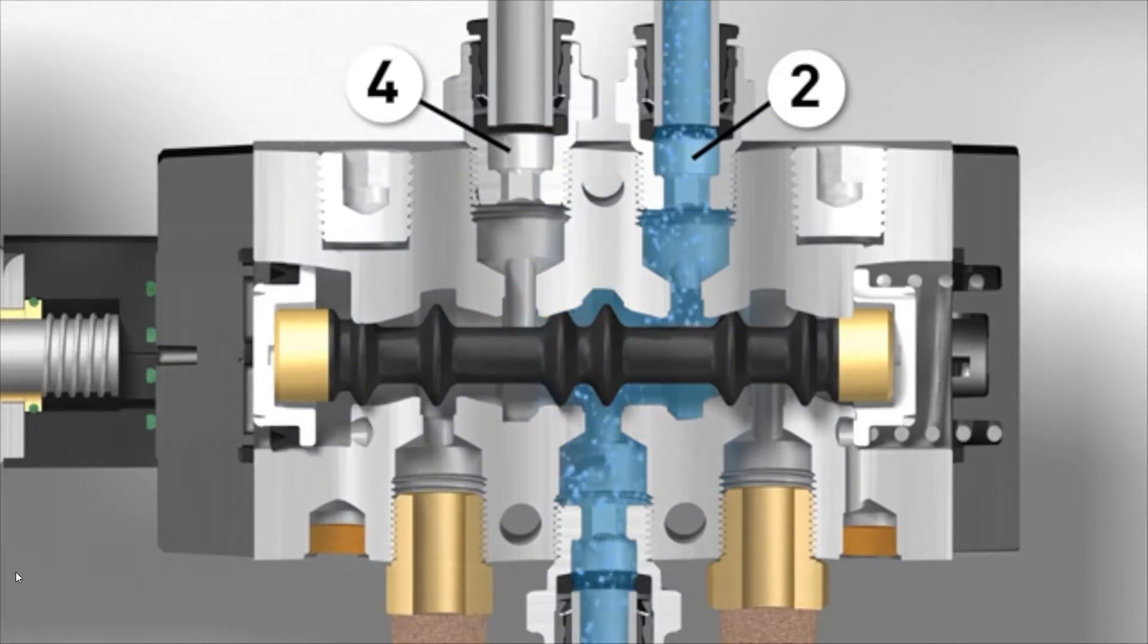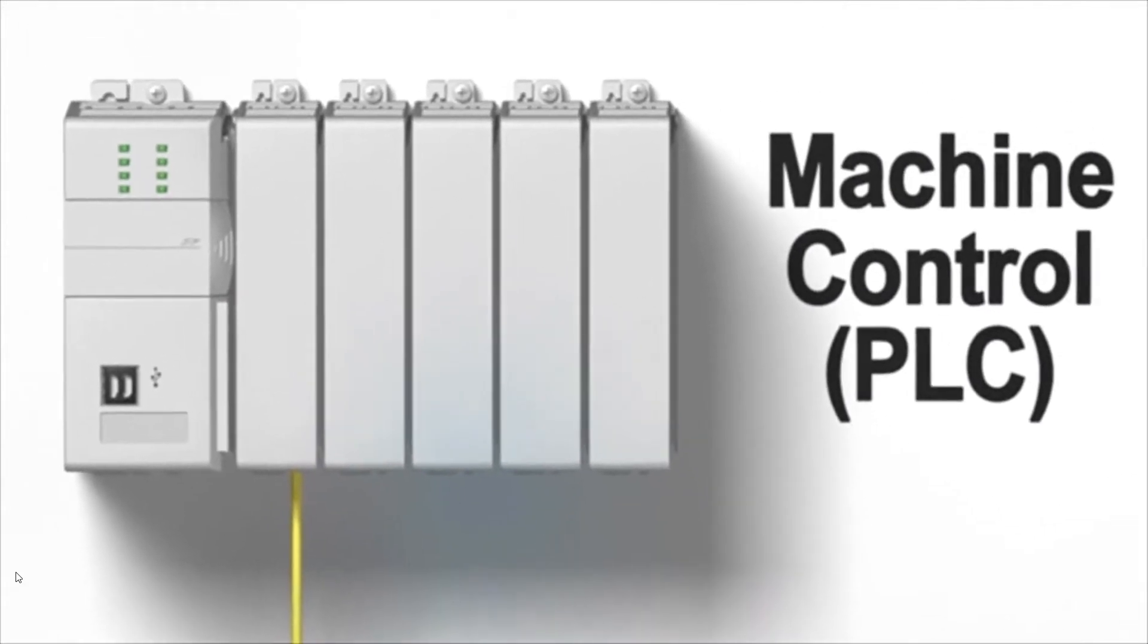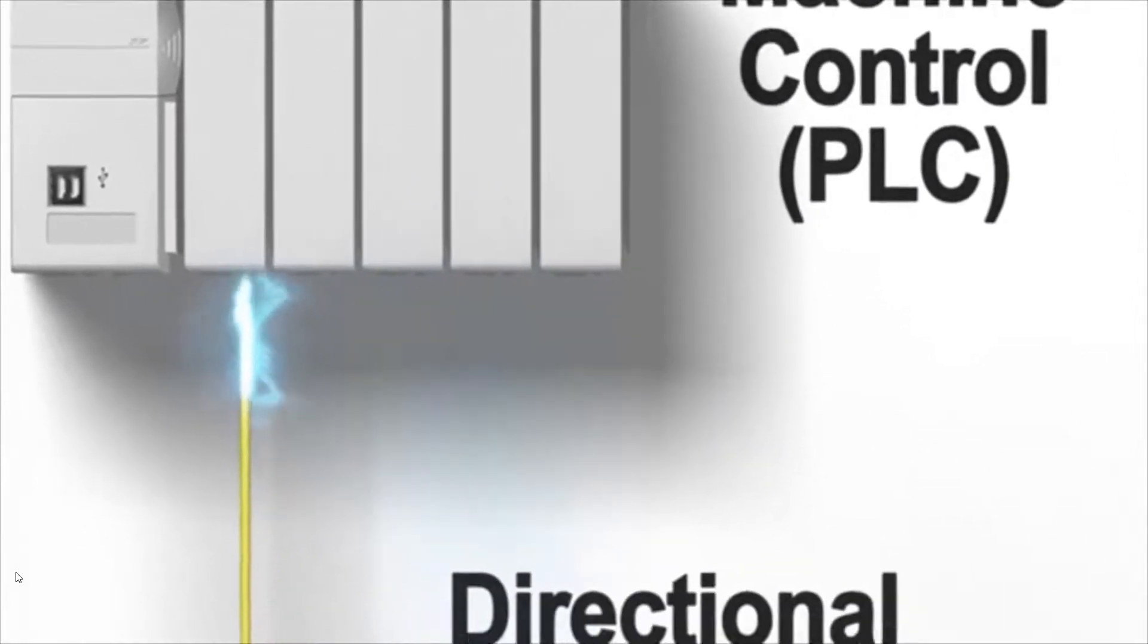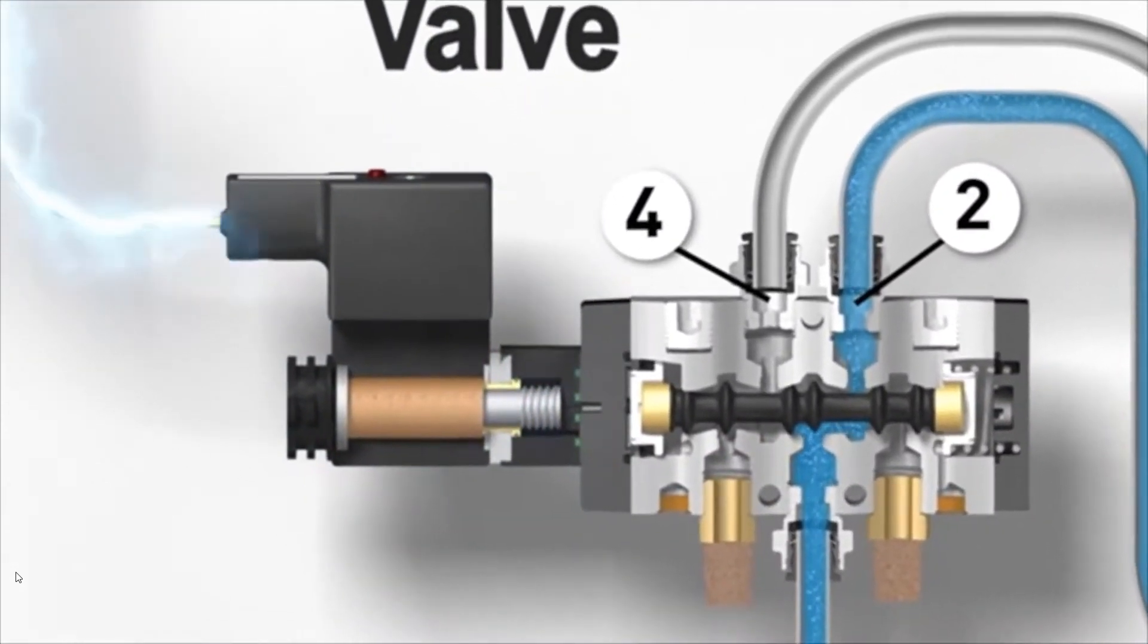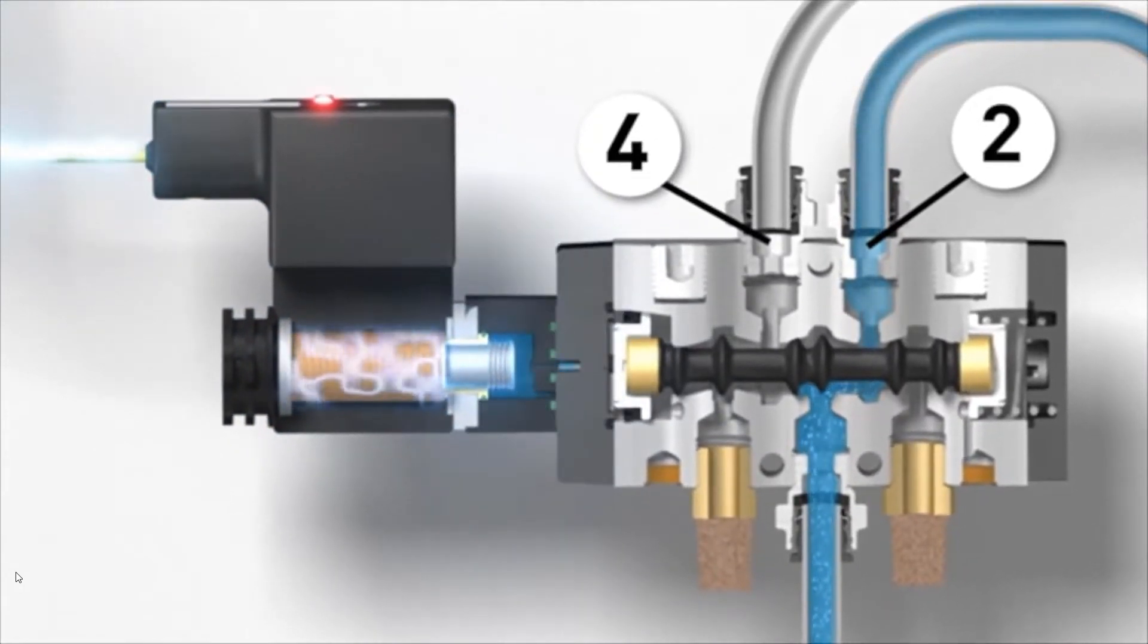In order to change the direction of the air to the number four working port, the valve needs to be turned on. In most automated equipment, a PLC, or Programmable Logic Controller, will instruct the valve to shift using an electrical signal. When the signal arrives at a portion of the valve called a solenoid coil, a magnetic field is created that pulls a plunger towards it.